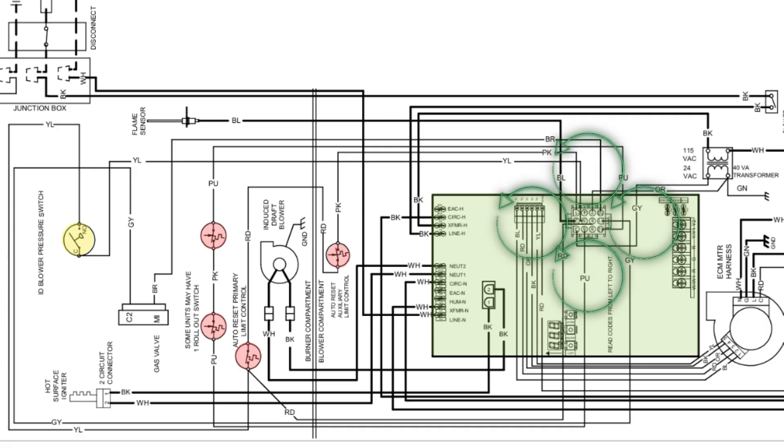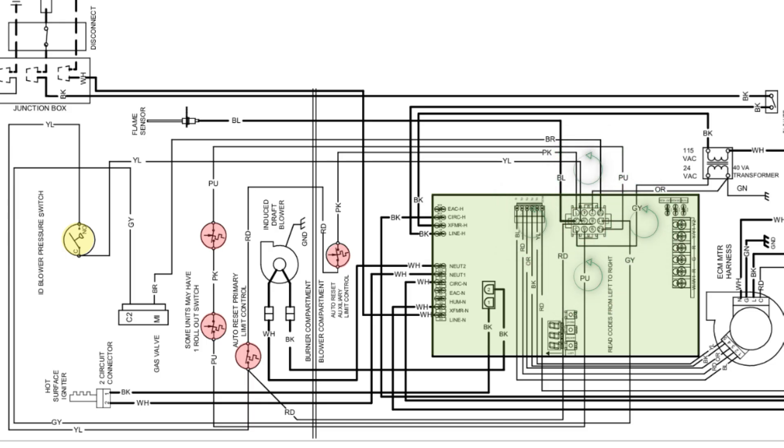Each component has its own power source and path back. But that's not the actual purpose of control board design with these Molex plugs. Whenever it comes to safeties in a burner circuit, whether it's a furnace, a hydronic boiler, or a steam boiler, all these safeties are always going to be wired in series.